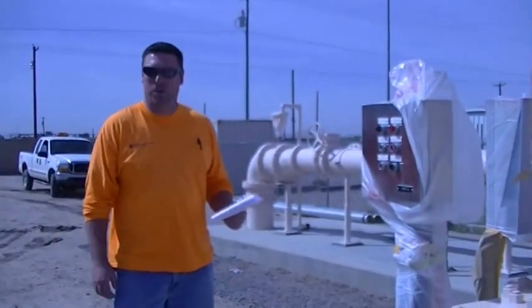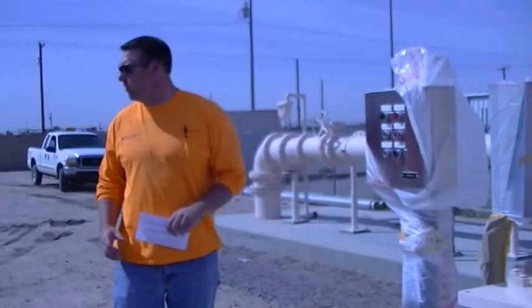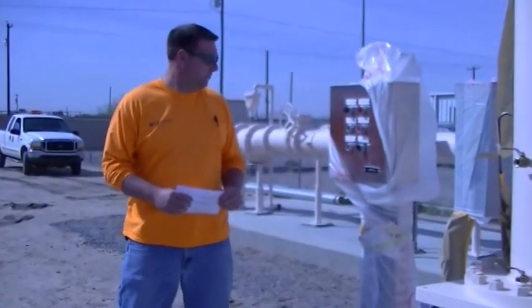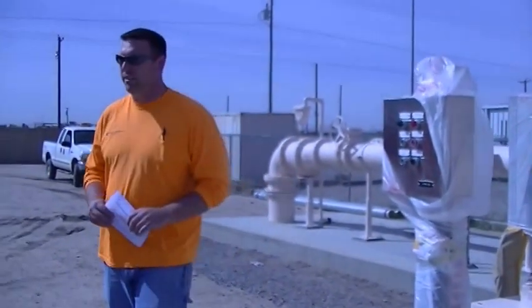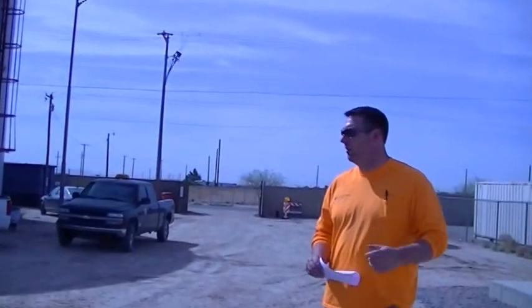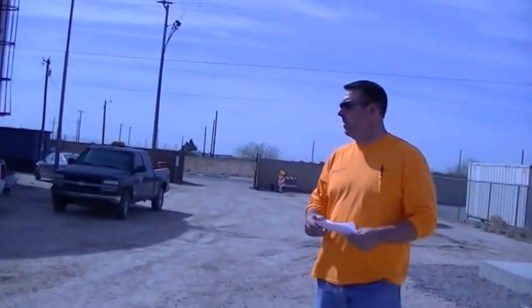So that's about it here. It's pretty straightforward. You guys can handle it. Dave, anything to add? The truth of the matter is the soft starts work the same way. You just don't have the potentiometer for speed control. So on is on. You'll ramp it up to full speed. Hit start, you'll bring the motor on, ramp up to full speed until it gets stopped.